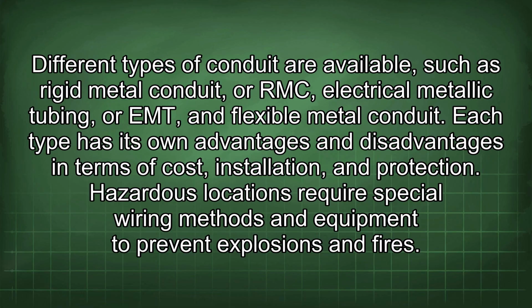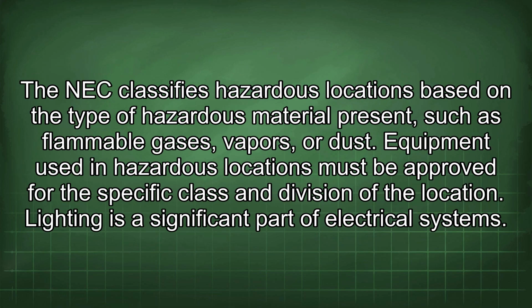Hazardous locations require special wiring methods and equipment to prevent explosions and fires. The NEC classifies hazardous locations based on the type of hazardous material present, such as flammable gases, vapors, or dust. Equipment used in hazardous locations must be approved for the specific class and division of the location.